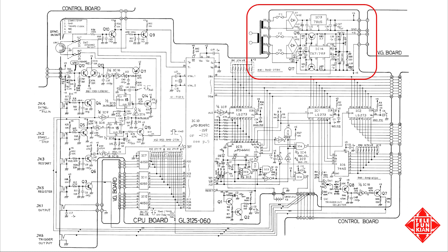AC power enters the instrument through a polarized grounded connector that's wired in one of 4 configurations depending on the destination market. The line cord is immediately fused before proceeding to either a single pole switch in North America or Japan, or a double pole single throw switch in Europe and the UK, where both line and neutral are switched in unison. Directly across the AC line lies C101, a 10 nanofarad 400 volt capacitor that acts primarily as an interference filter, preventing reintroduction of noise into the line.